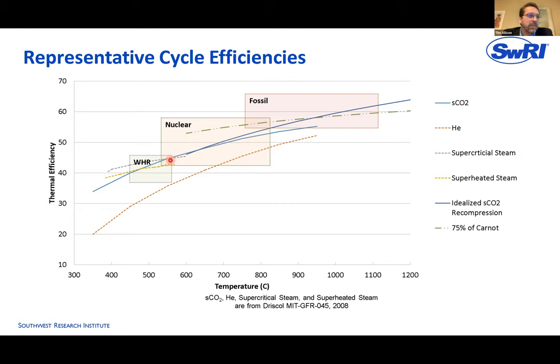In the waste heat recovery range, we're getting close to crossover in some cases between steam and SCO2, depending on how many stages of reheat, pressure splits, or casings there are in the steam turbine. There's some room where SCO2 has higher efficiencies than steam for waste heat recovery, and at higher temperatures, 700 C or more, SCO2 is a clear winner in terms of thermal efficiency.